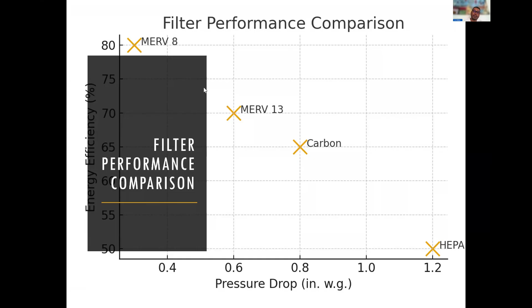What I drafted here was a little chart that I felt would help prove my point. On the bottom, the y-axis, I think that's the y-axis, shows pressure drop. And the left, the x-axis, shows energy efficiency. Now that energy efficiency actually refers to the full unit energy efficiency versus the specific filter or a specific fan. And what we can see with a MERV 8 having a very low pressure drop stands to reason that you're going to have a more efficient fan.